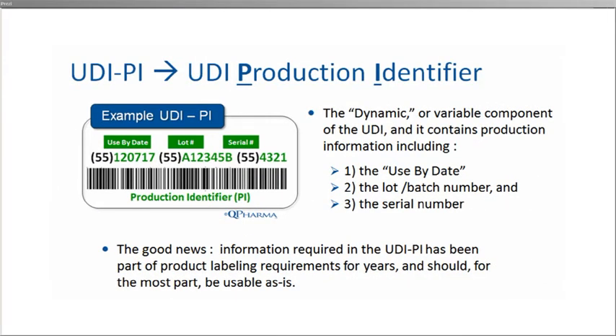The second part of the UDI is the production identifier, or UDI-PI. This is the dynamic component of the UDI, and changes with each production run or batch of the product. The UDI production identifier captures variable content like the use-by date, lot, batch number, and serial number if required. The good news is that most of the production identifier information is already being captured, as these elements have long been part of labeling requirements.